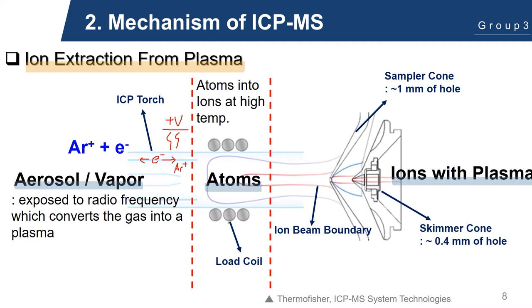The ions are extracted from the plasma into the interface through a 1 mm sampling orifice, and then a 0.4 mm skimmer cone into a high vacuum region containing ion lenses and a mass analyzer. Electrostatic lenses focus the ion beams by only selecting positive ions into the reaction cell and removing the unwanted neutral species.